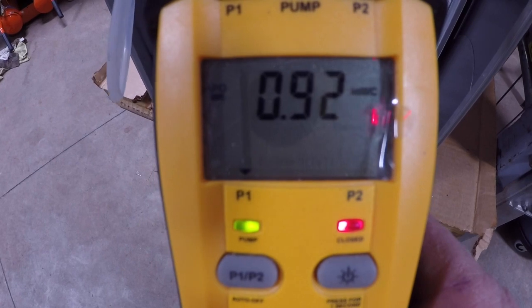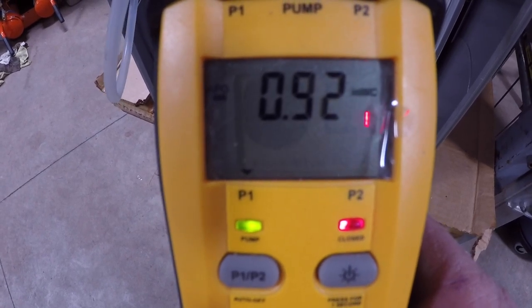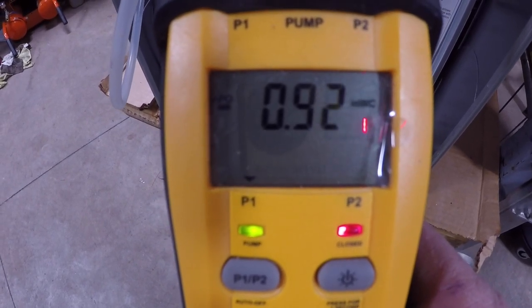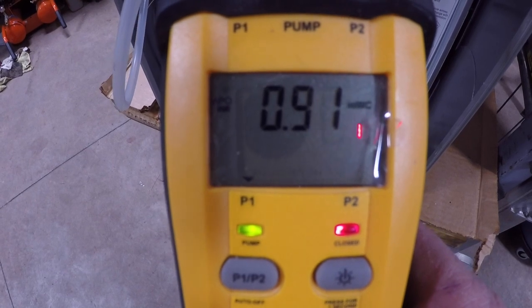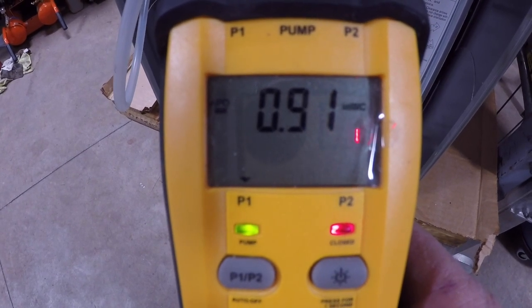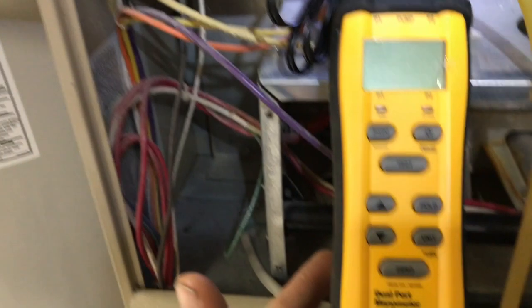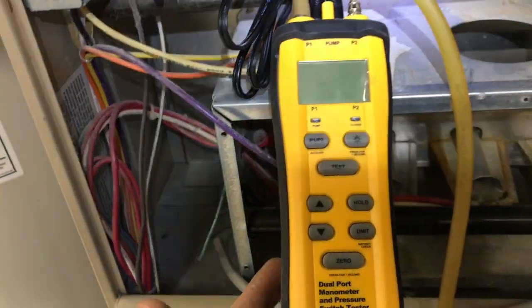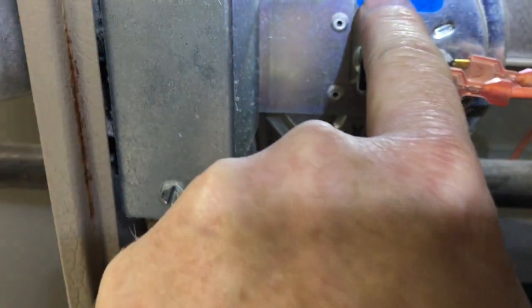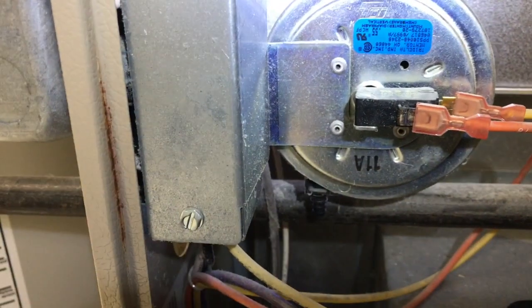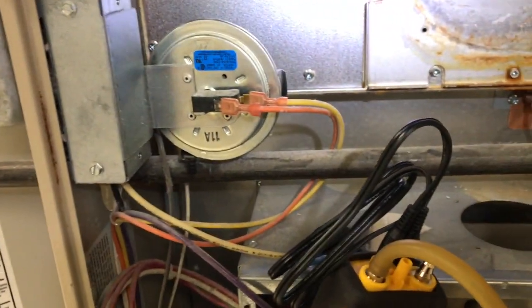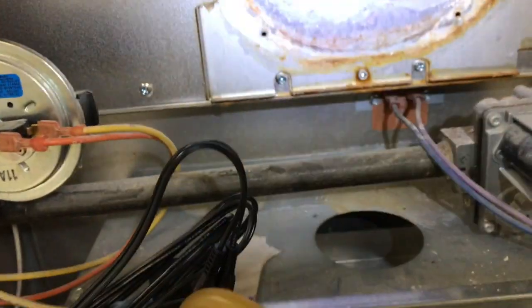That pressure switch closed. So if that's where it's supposed to close, that means the switch is operating like it's supposed to, and I need to look somewhere else in the furnace. It's not a pressure switch issue. It might be something else. So I tested the pressure switch with my dual port manometer here, and it was making and breaking like it's supposed to. It's rated at 0.55 inches of water column fall. So I actually checked the inducer motor, and it was not pulling 0.55.